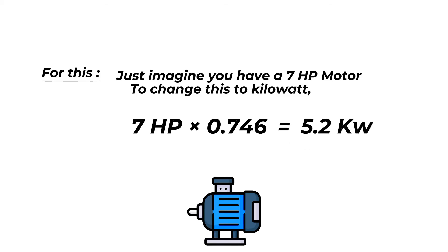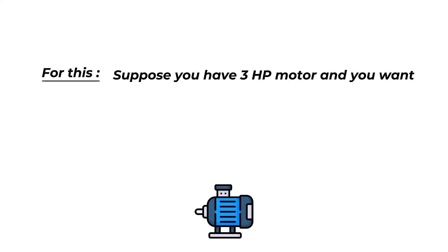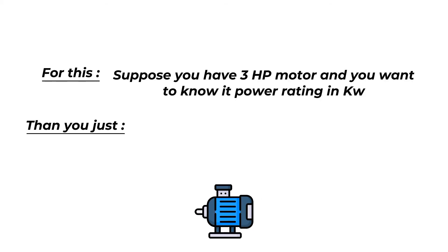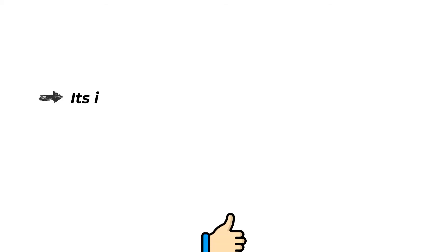Let's look at one more example. Suppose you have a 3 HP motor and you want to know the power rating in kilowatt. Then you just need to multiply 3 HP with 0.746. You will get 2.2 kilowatt answer. It is so easy now.